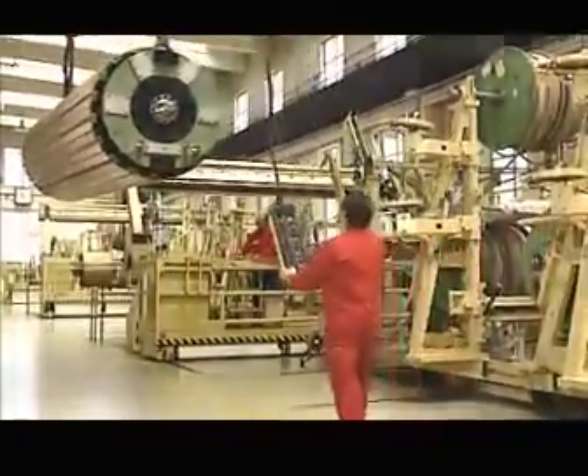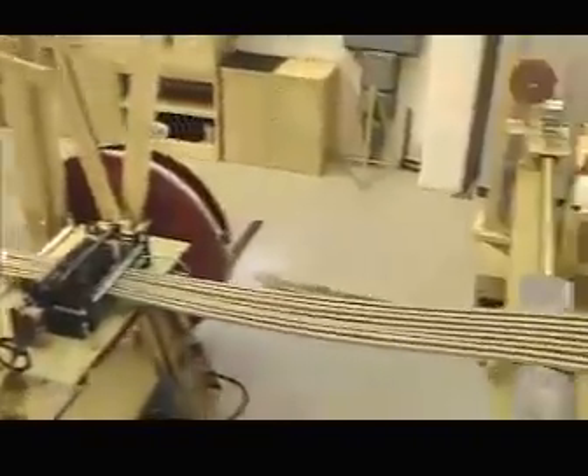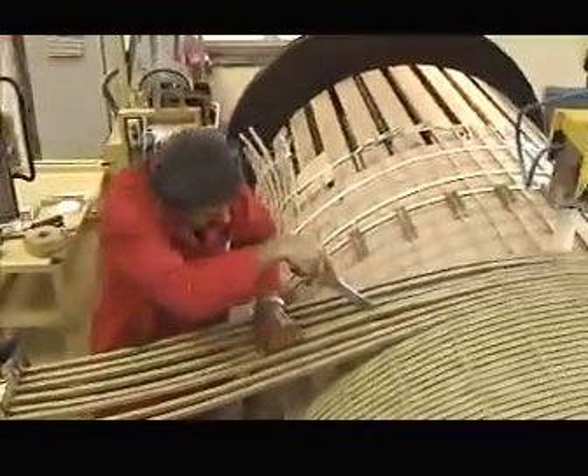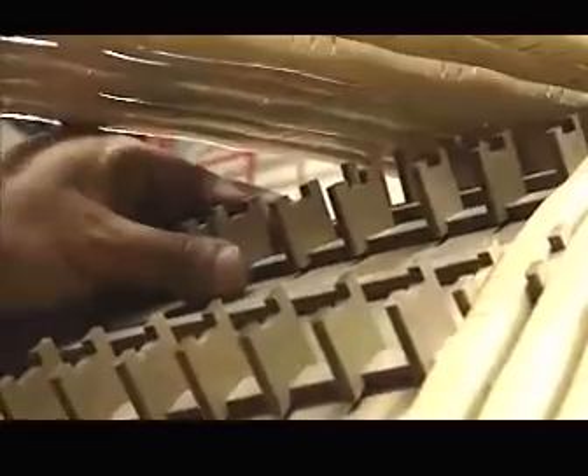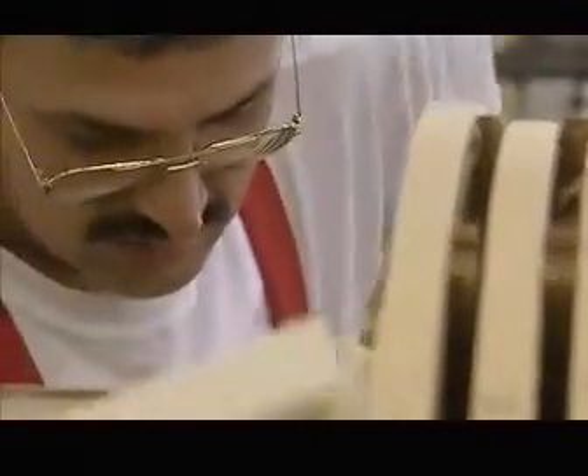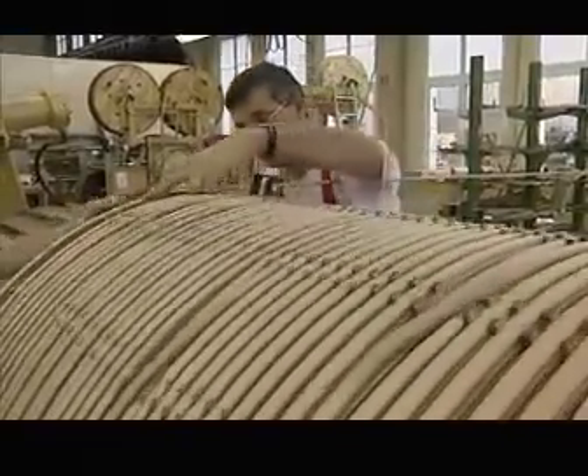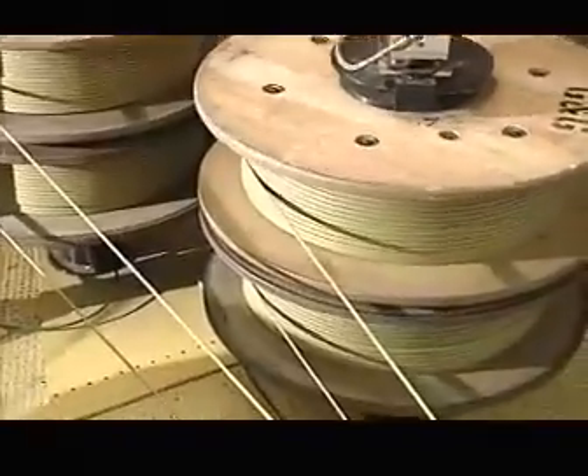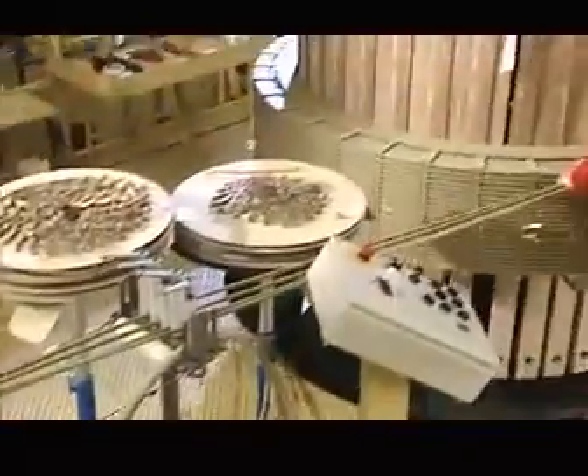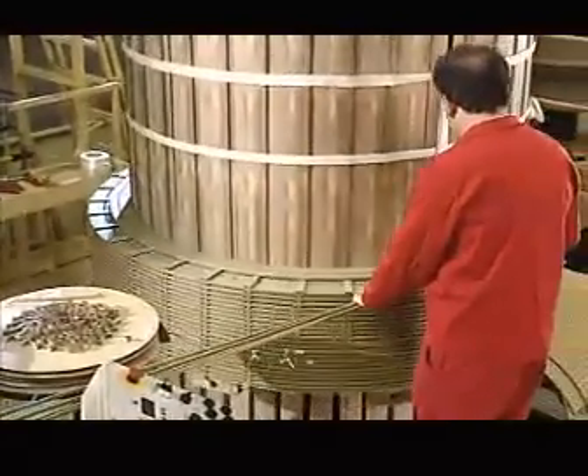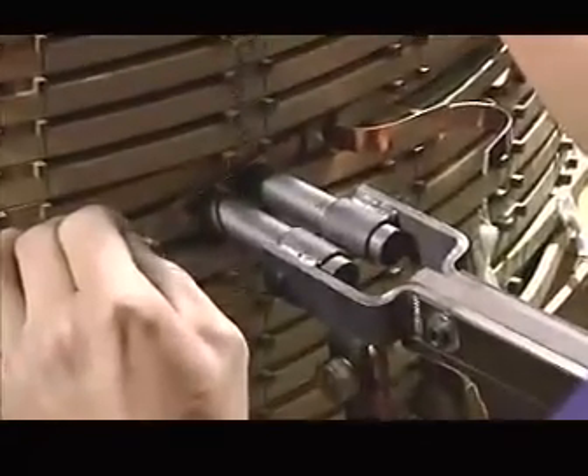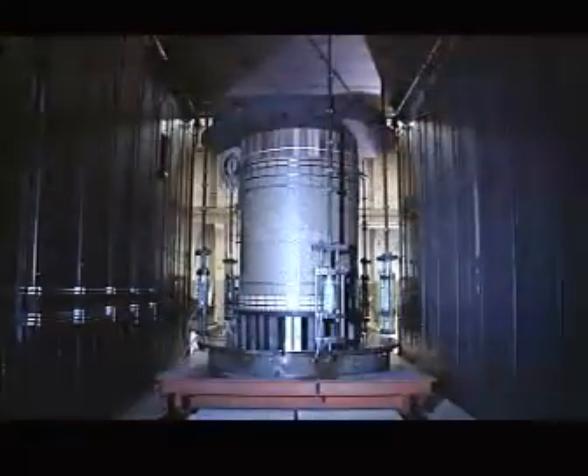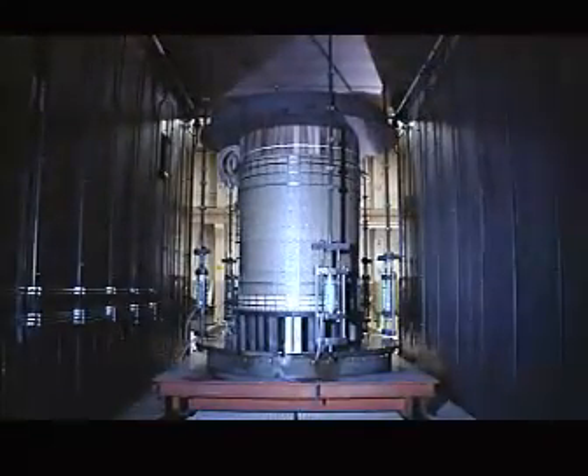The windings are produced in special clean areas. Layered windings made of stranded conductors are normally used on the low voltage side. The insulated conductor is wound one layer at a time under constant pressure and tension. Coils for high and very high voltages are wound on vertical winding benches in the form of continuously wound disc coils, or else as single coils. Then the windings are dried under constant pressure in large vapor phase drying ovens.